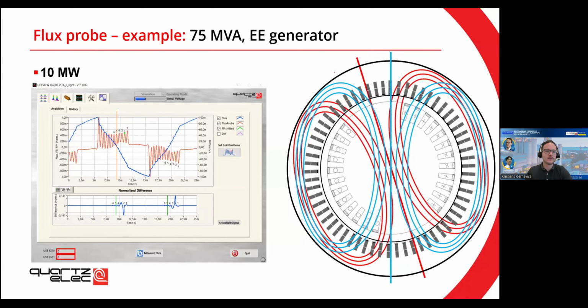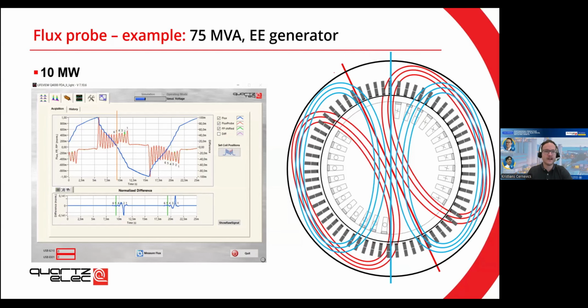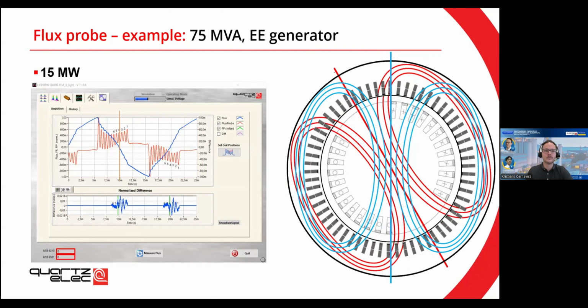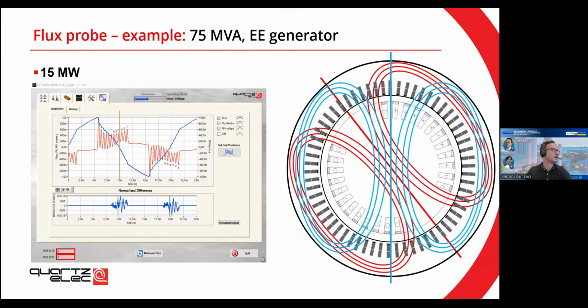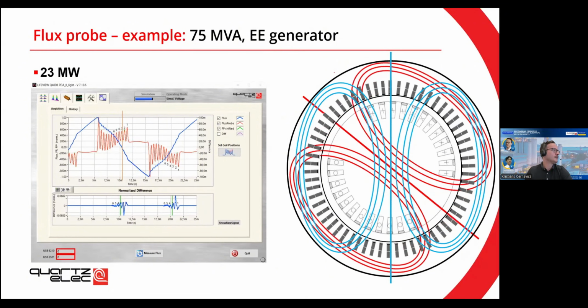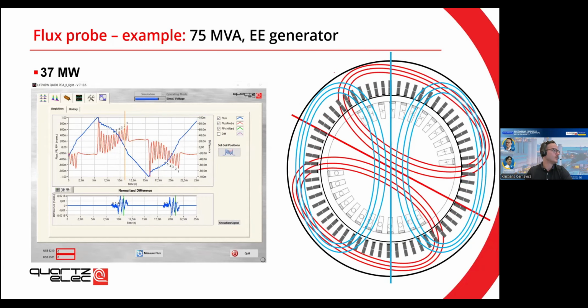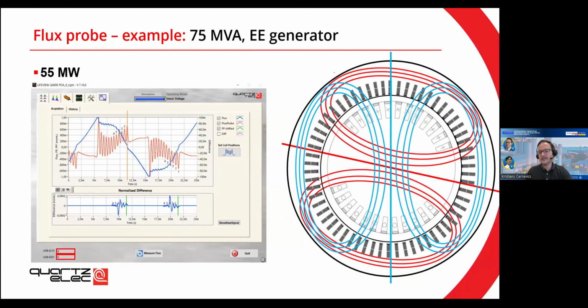Once we increase the load, the orange line now goes through coil number 5, 4, we increase the load even further, 3, we increase the load further, 2, and 1. So ideally, once you do the condition monitoring of your flux, your coils, you would go through different loads to uncover different coils for higher sensitivity measurements. If this is not possible, and you stay at the same load, this is not critical or dangerous. It's just that the sensitivity of the measurement is going to be a little bit lower.